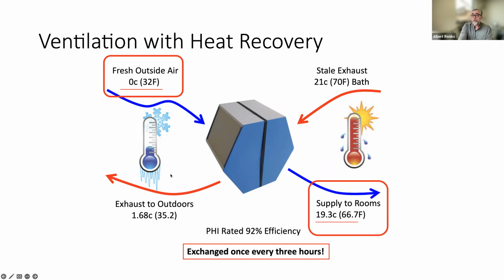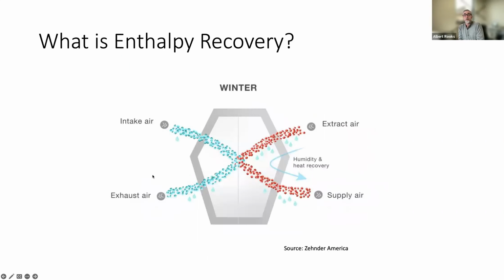And we can generally do that once every 2 hours, refresh the entire content of the building in airflow, or once every 3 hours. That's called the air exchange rate. And we'll get into the mechanics of that a little more. But in addition to heat exchange, we can also do enthalpy recovery or moisture recovery. So if we're in my climate here in the Pacific Northwest, it's generally pretty tolerable outside. It doesn't get super hot, doesn't get super cold, at least so far. And the inside, we always try to keep it about 70 degrees, 50 to 60% relative humidity, or 40 to 60% relative humidity. And it's just kind of magic, we just bring in, when it's a rainy day up here and it's nasty outside, it's 90% humidity and it's 40 degrees or something like that.